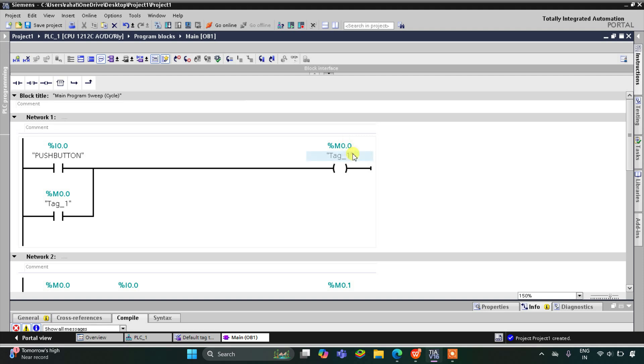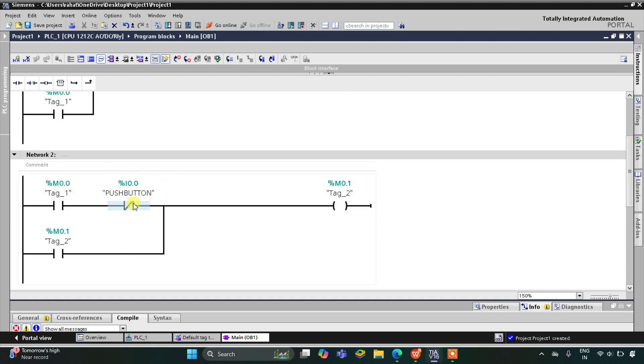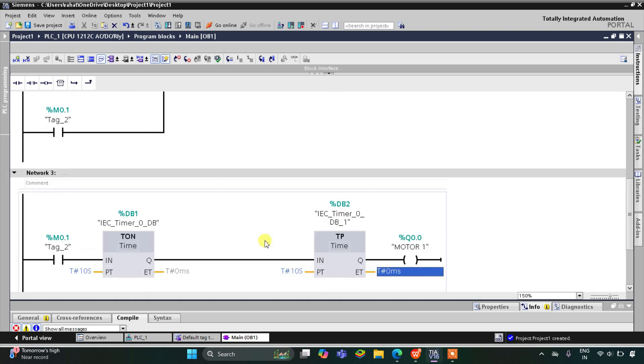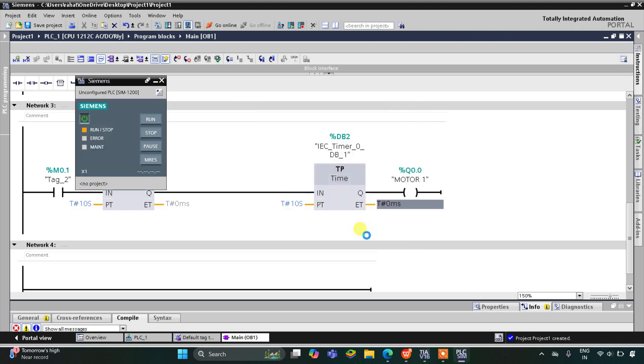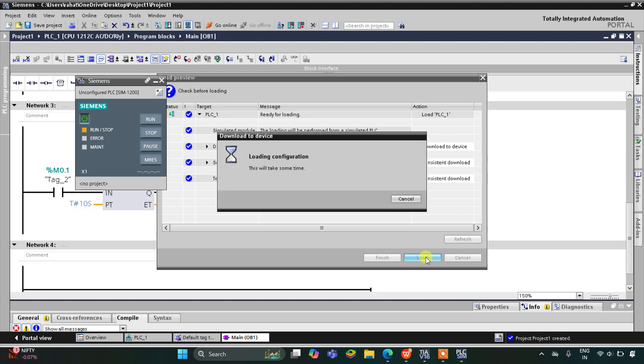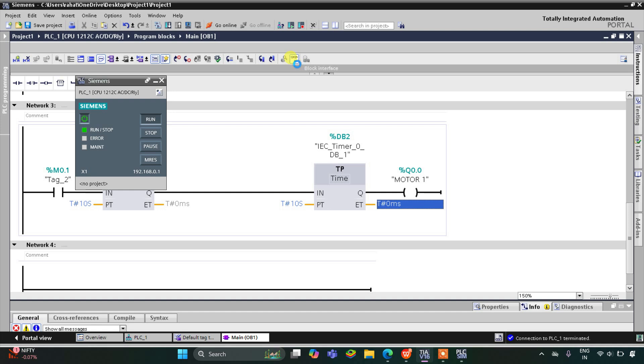As you can see, when push button is pressed M0.0 gets true, and when it is released M0.0 still remains true. As M0.0 is true and the push button is released — meaning it is off — current flows through, M0.1 gets true and remains true. When M0.1 gets true, it will wait for 10 seconds, after which Motor 1 turns on for 10 seconds. I will start the simulation now.